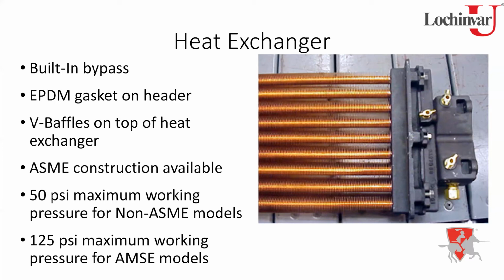A lot of people have asked me in the past, are those copper fins brazed on, welded on, or what have you? No, they're not. It's one solid piece. They're just extruded from a thicker piece of copper tubing. So do keep that in mind. And that's another reason why we do have to keep this stuff cleaned up once a year, because those copper fins are pretty close together, and things can build up over time in between them. So we like to make sure that those flue gases can really pass in there.